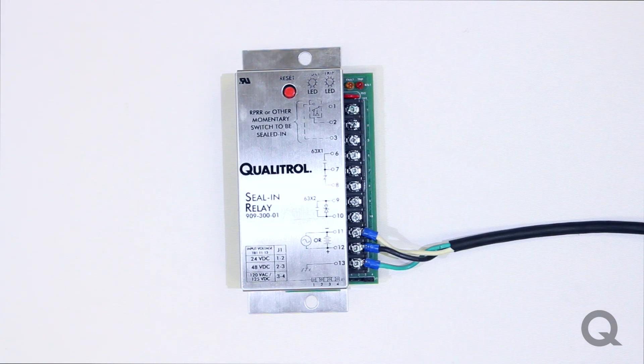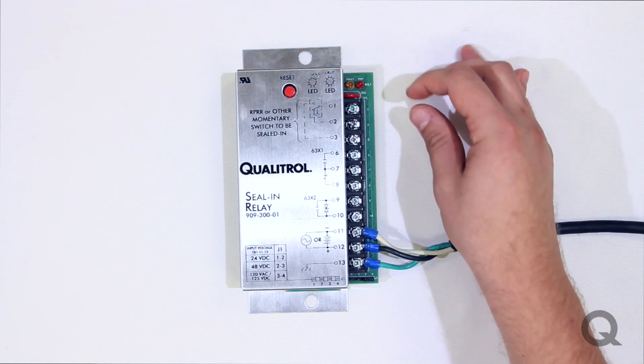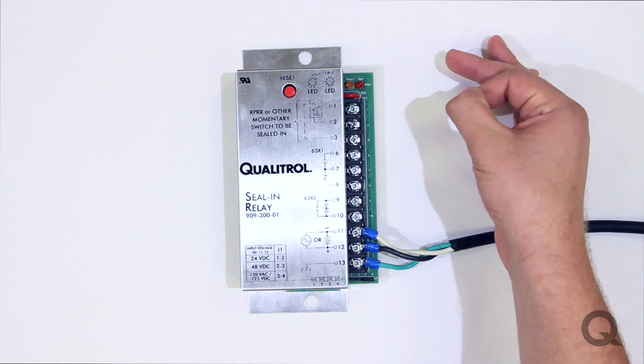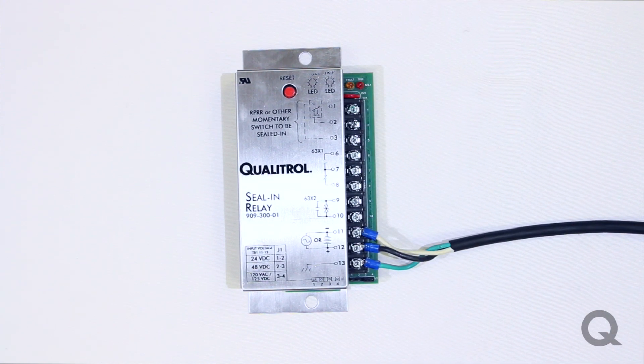Another feature on our new Seal-In Relay: if you are running AC or DC voltage, always make sure you ground terminal 13. Another question we get a lot is: can I run a form A contact instead of a form C contact in terminals 1 through 3? The answer is yes — the red trip light will not go off, but the Seal-In Relay will still function as normal.